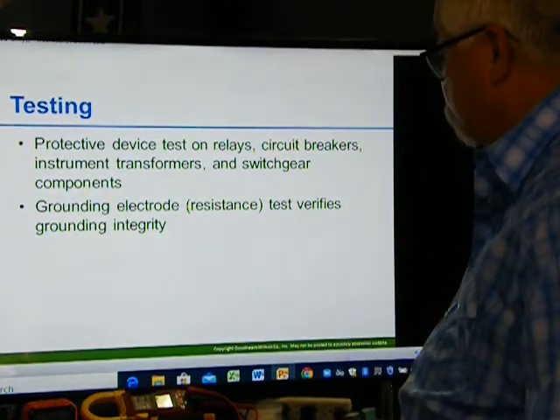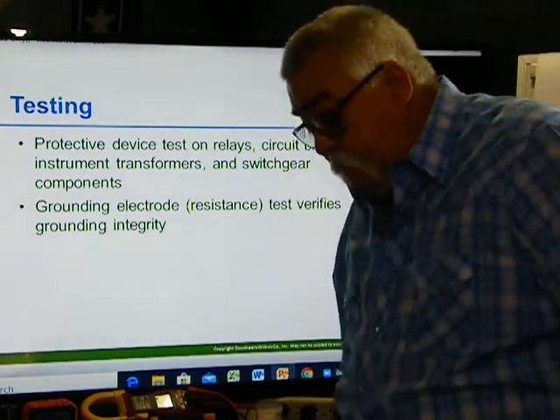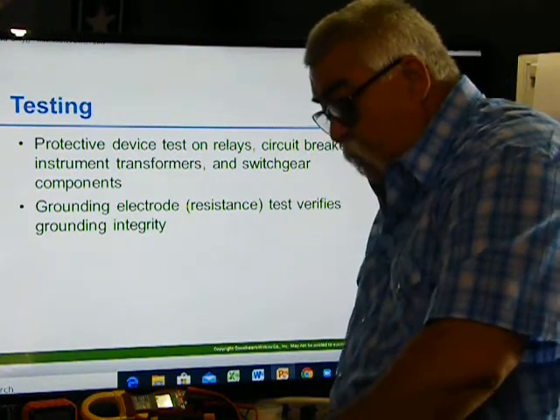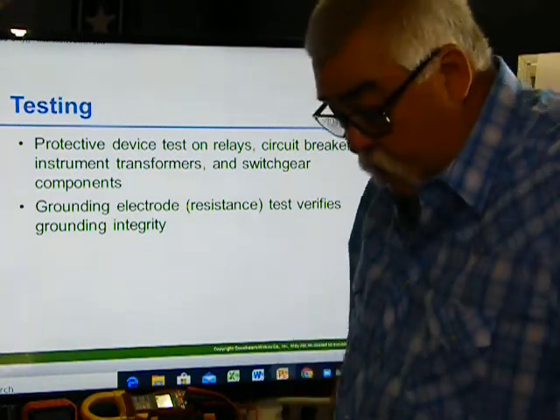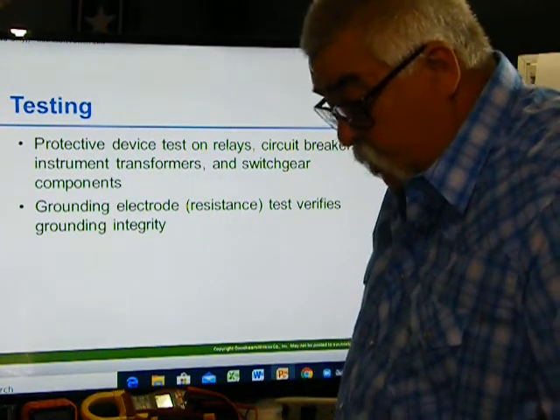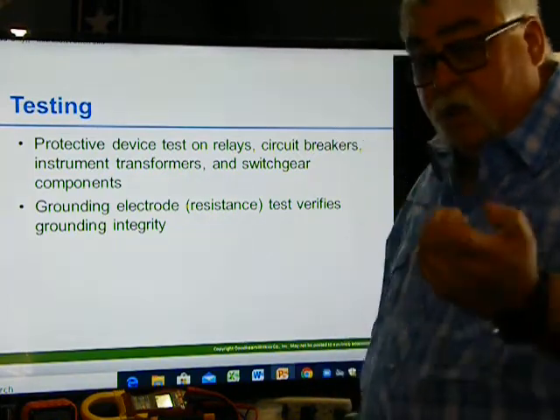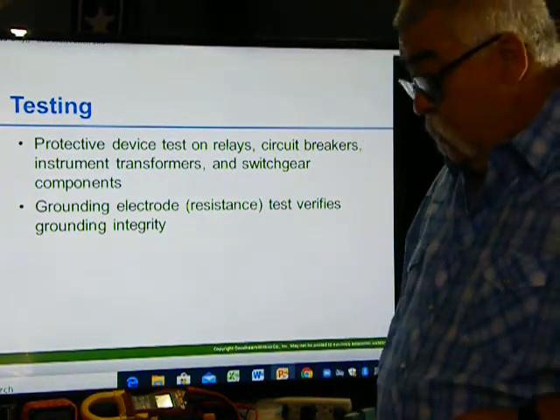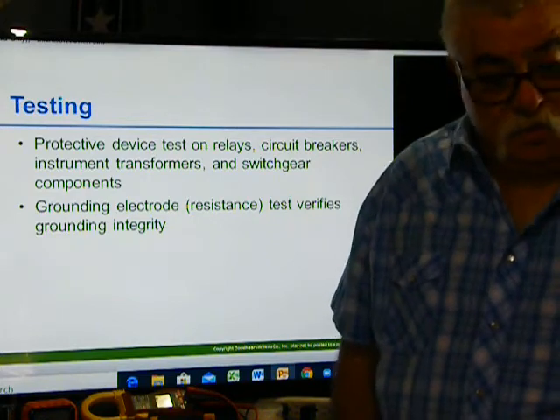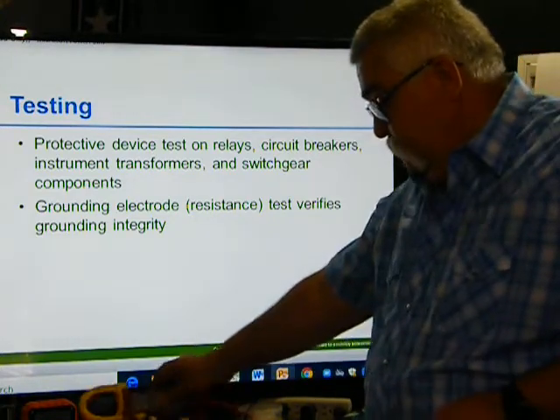Grounding electrode resistance test verifies grounding integrity. So checking your grounding. Grounding test, so you can use a megger. They make one like for ground rod. You can use your amp probe to find out, you know, what's your resistance to ground.